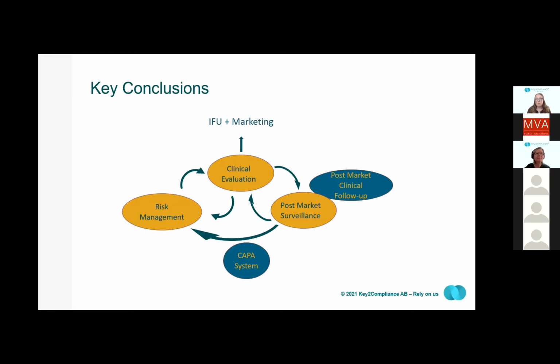And then you have the post-market surveillance that could reveal new risks, or you could detect trends. And through your CAPA system, you would then need to analyze those new risks in the risk management and make an update of your benefit risk analysis. And if those risks are also clinical risks, sorry, you would also need to update the clinical evaluation. And so it goes on. And you might also identify a gap in your clinical evidence, and for example, that you need to cover with doing a post-market clinical follow-up study that Robert told you about earlier.